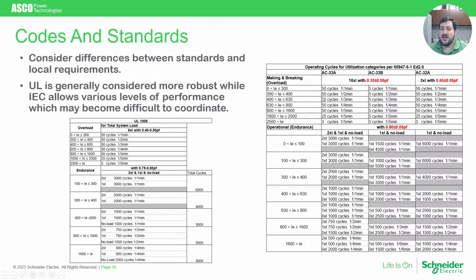For example, the IEC standard allows for different category levels or utilization categories, such as AC 33A, 33B, 32A, of which you can qualify to any of those that you select. However, the level of performance between these standards and the testing required to qualify is significantly different between each of those.